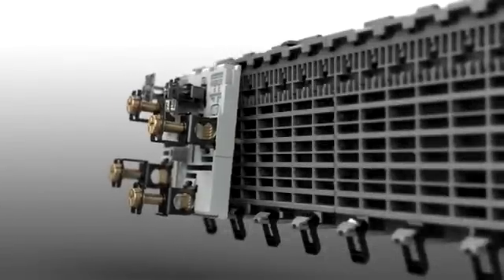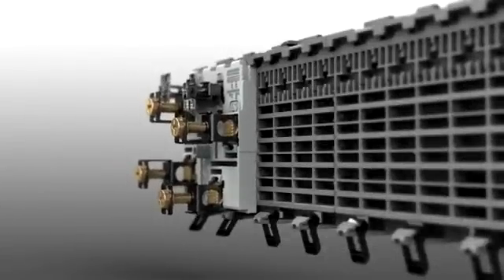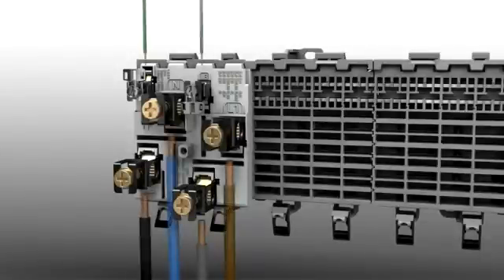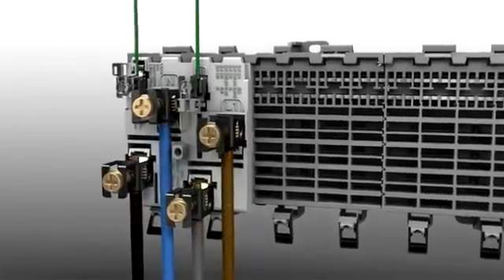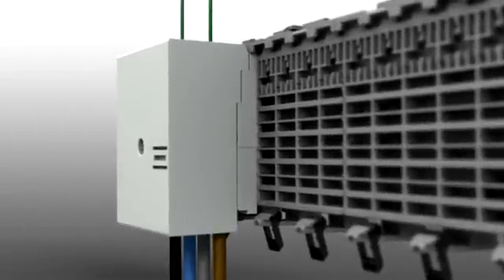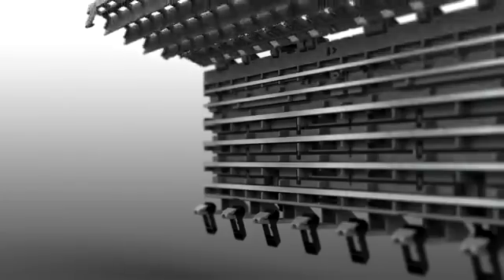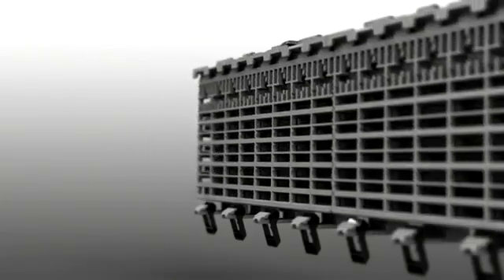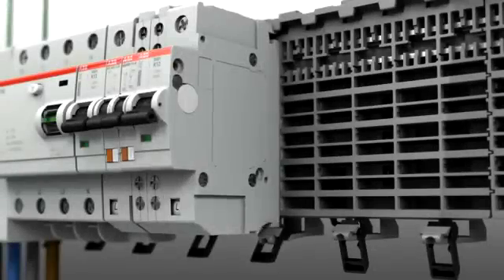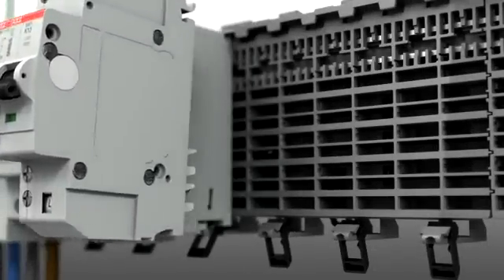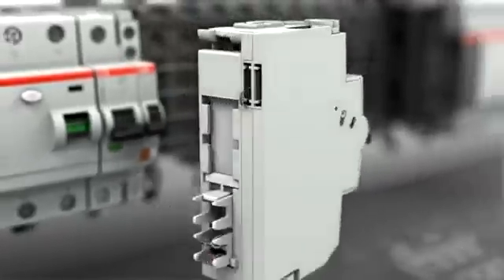The power can be supplied to the bus bar system via an incoming terminal block or directly via a protection device. The bus bar system is closed in a way that ensures full protection against direct contact. This enables load-free plugging in and unplugging of live devices without the need for personal safety equipment.